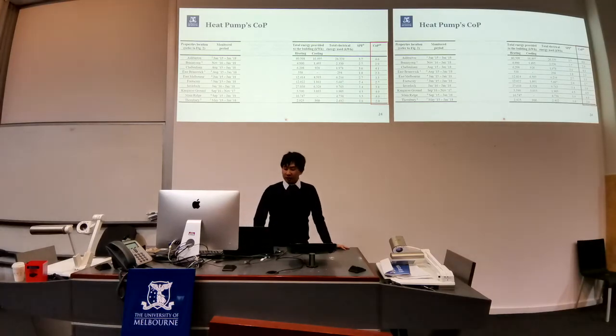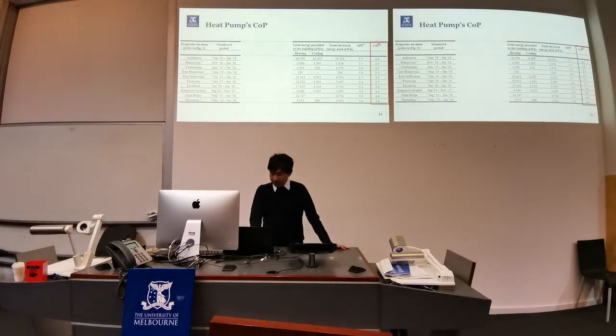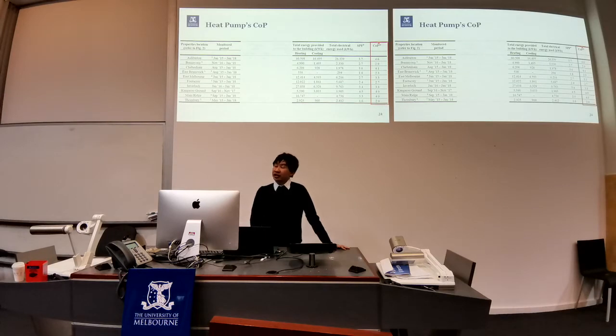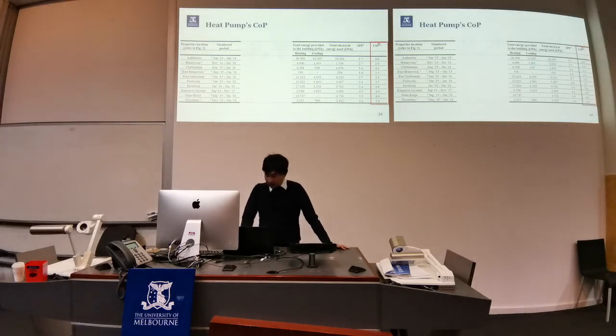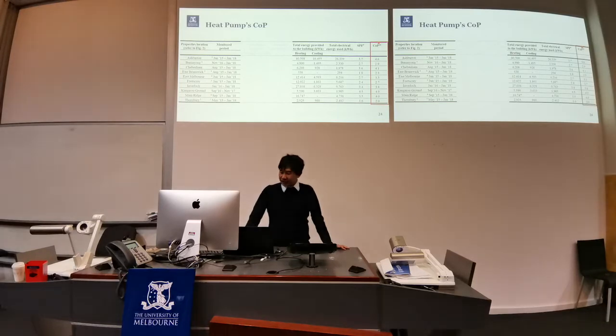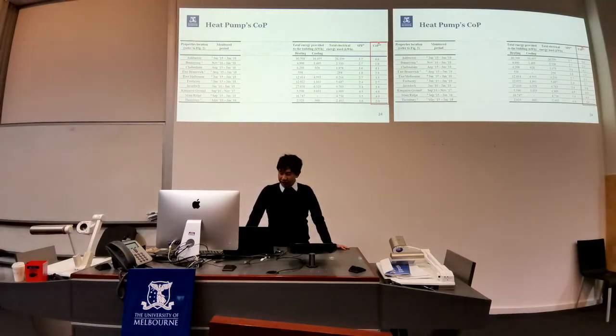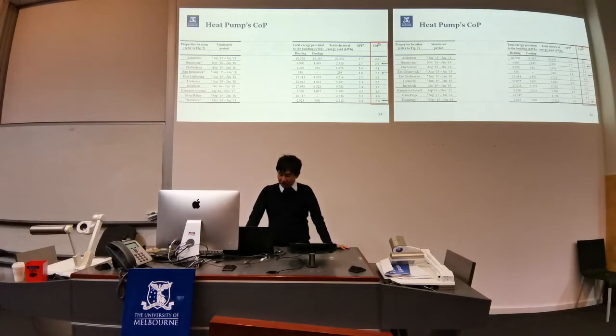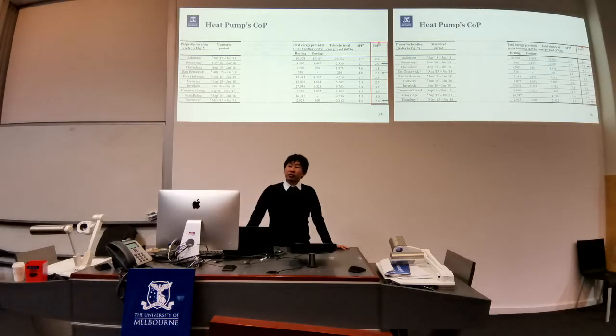The coefficients of performance are provided here. This is a measure of efficiency, depending on the amount of thermal energy provided to the building in relation to the electrical energy consumed by the system. Unfortunately, there are several systems which have relatively low efficiency, such as the one installed here. Those are the properties that were retrofitted with the locally made heat pump.